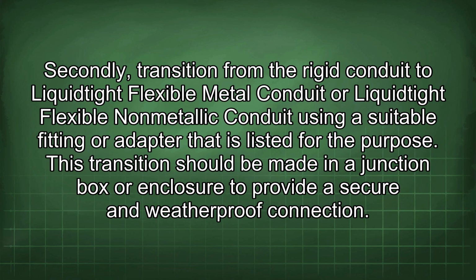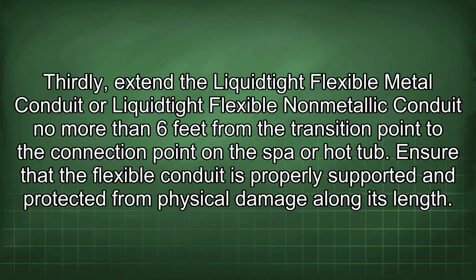Secondly, transition from the rigid conduit to liquid-tight flexible metal conduit or liquid-tight flexible non-metallic conduit using a suitable fitting or adapter that is listed for the purpose. This transition should be made in a junction box or enclosure to provide a secure and weatherproof connection. Thirdly, extend the liquid-tight flexible metal conduit or liquid-tight flexible non-metallic conduit no more than 6 feet from the transition point to the connection point in the spa or hot tub. Ensure that the flexible conduit is properly supported and protected from physical damage along its length.